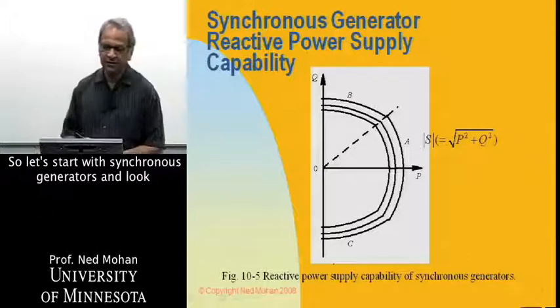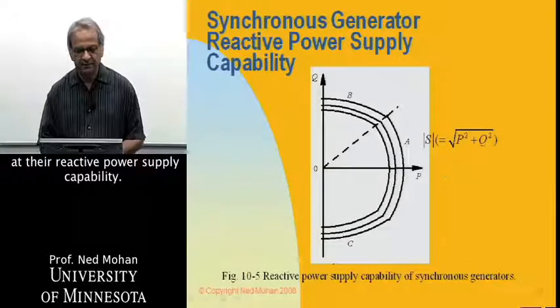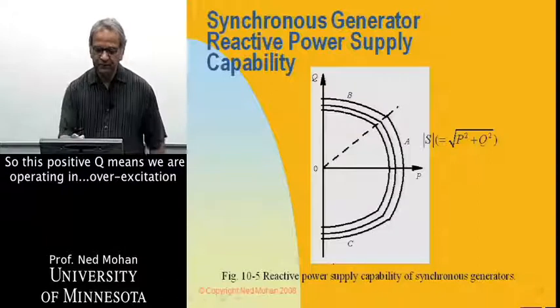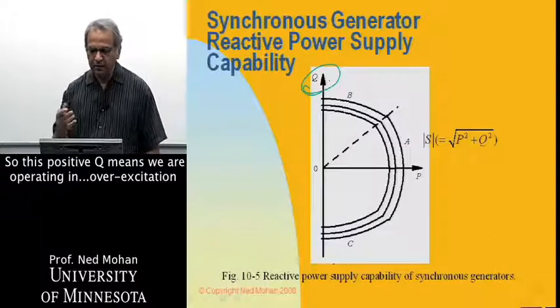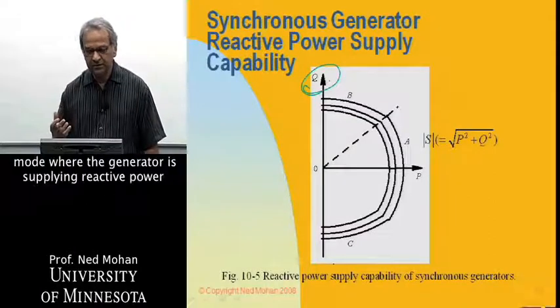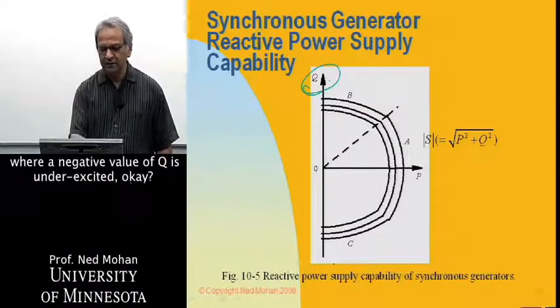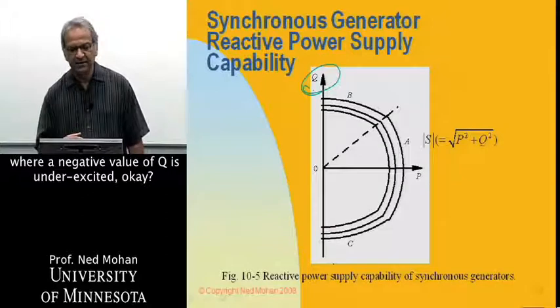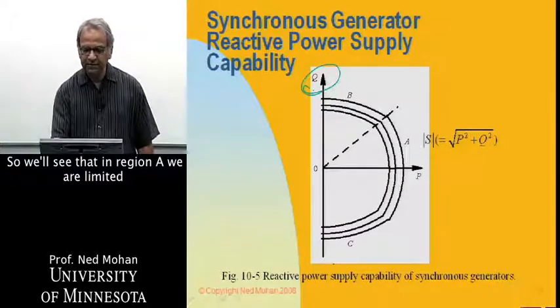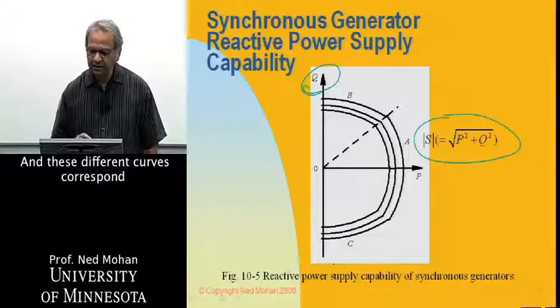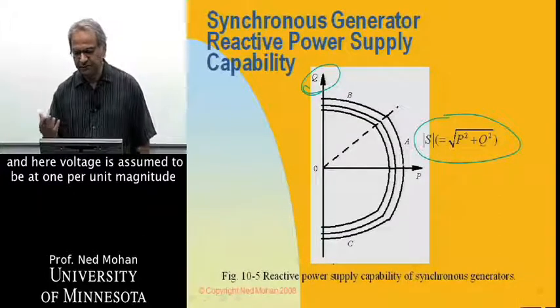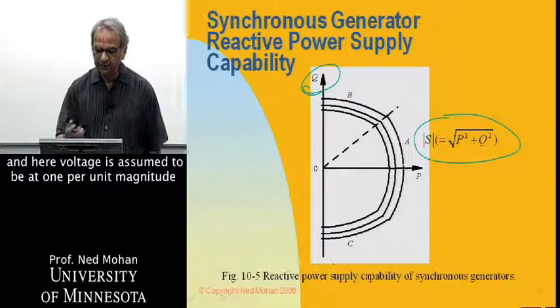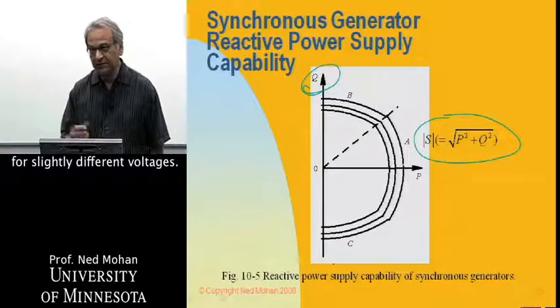Let's start with synchronous generators and look at their reactive power supply capability. Positive Q means we are operating in over-excitation mode where the generator is supplying reactive power, whereas negative Q is under-excited. In region A, we are limited by the heating of the machine. These different curves correspond to different hydrogen pressures for cooling, and voltage is assumed to be at one per unit magnitude, though similar curves can be obtained for slightly different voltages.